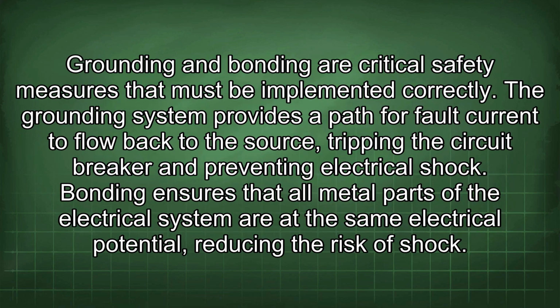Grounding and bonding are critical safety measures that must be implemented correctly. The grounding system provides a path for fault current to flow back to the source, tripping the circuit breaker and preventing electrical shock. Bonding ensures that all metal parts of the electrical system are at the same electrical potential, reducing the risk of shock.